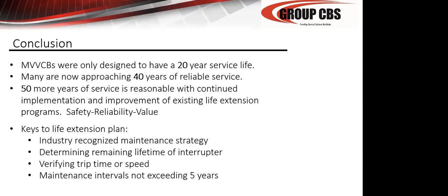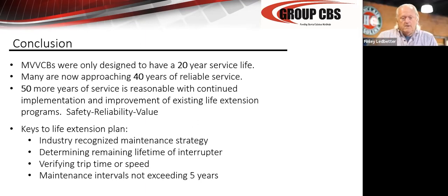What frequency should we do speed tests, or I guess timing tests? There you go. Well, it's very quick, okay? Breaker timing testing is very quick. If you have a modern timer that's integrated, where you don't have to hook up a separate power supply and use a bunch of alligator clips, you can time the breakers in just a couple of minutes. So there's no reason not to do it, especially a parting test, which you can do in a couple of minutes.